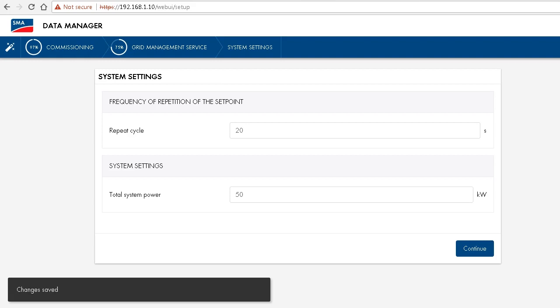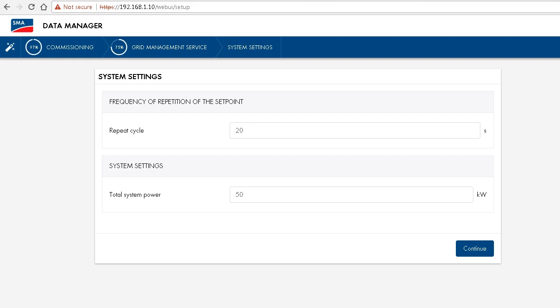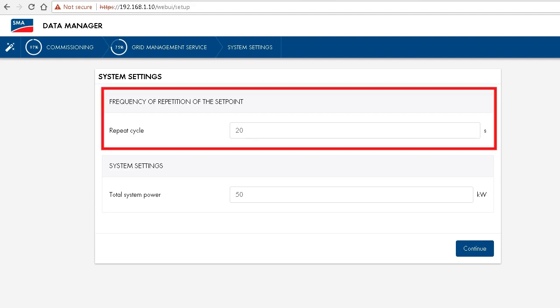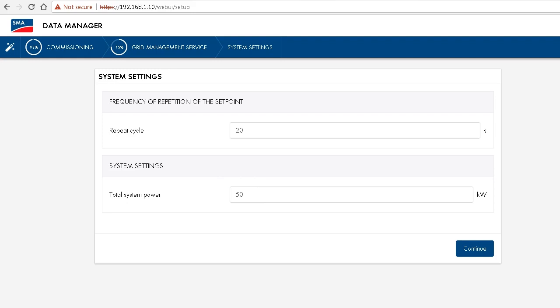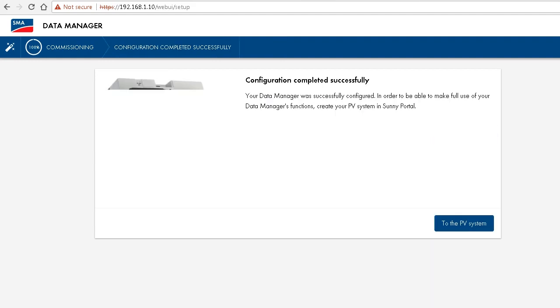We just have the last chance now, as a setup, to set the frequency of repetition for that set point, active power set point. This is yet another thing that the grid operator needs to tell us. So if the grid operator is fine with the frequency repetition, 20 seconds, and the defined system power, that is actually the total power of all the PV inverters connected to the system, then that is fine as well. Click on continue and we're done.